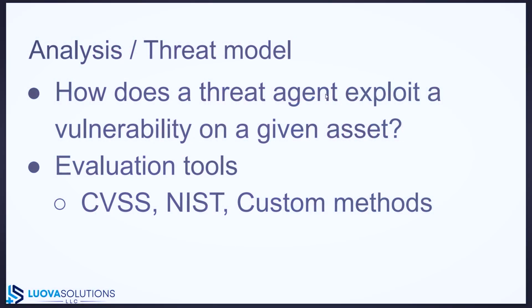All right, next slide. All right, so once I have all three of these tabs figured out, that's when I want to go through and bring it all together to create a comprehensive cybersecurity risk analysis. So that's where I ask the question, how can this specific threat agent exploit a vulnerability on a given asset? And so I create risks on that analysis based on every single one. So a vulnerability could have multiple entries on this table, depending upon how it affects different assets of the system and how different threat agents could exploit that vulnerability in order to find more information about the system or gain control over your medical device.